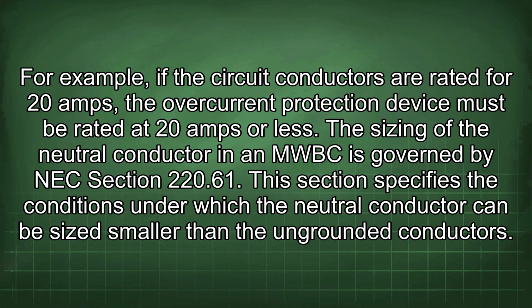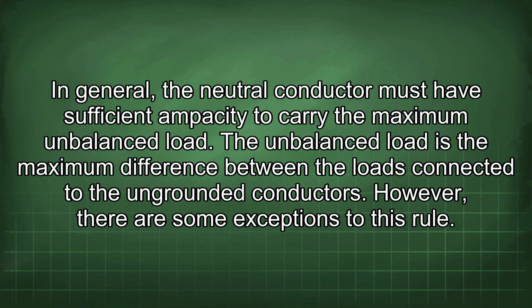The sizing of the neutral conductor in an MWBC is governed by NEC Section 220.61. This section specifies the conditions under which the neutral conductor can be sized smaller than the ungrounded conductors. In general, the neutral conductor must have sufficient ampacity to carry the maximum unbalanced load. The unbalanced load is the maximum difference between the loads connected to the ungrounded conductors. However, there are some exceptions to this rule.